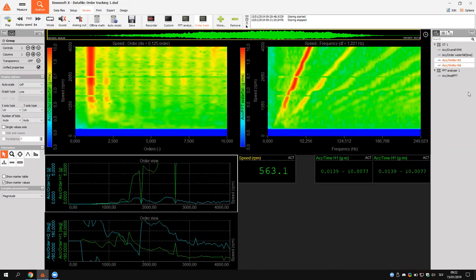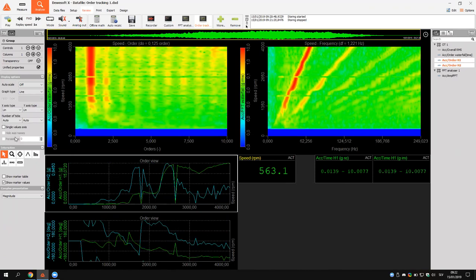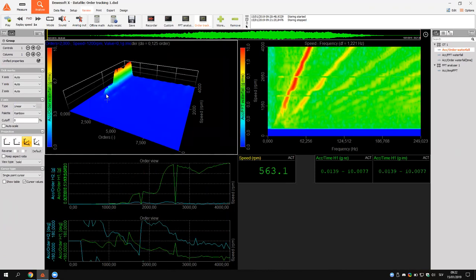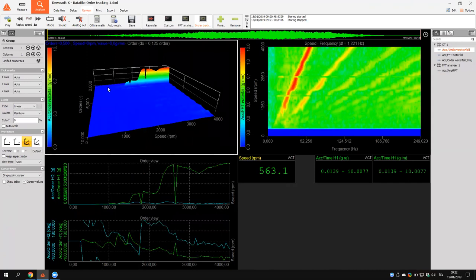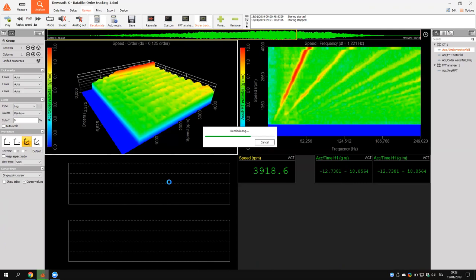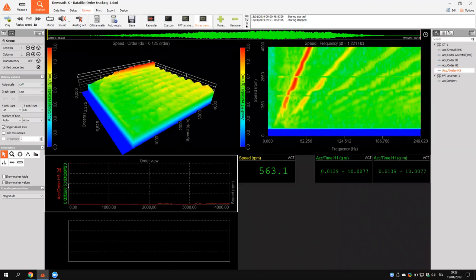Looking at the 2D graph, these are my extracted orders — order number one and order number two. Changing the projection, it is similar to a slice of the order waterfall showing my extracted order curve. If I want to add the third order, it's very simple: go back into setup, type in three, go to review, recalculate, and display all three orders simultaneously. The orders are complex channels, so we can also see the phase of the orders, which is an important parameter.